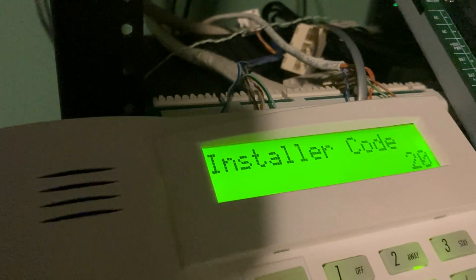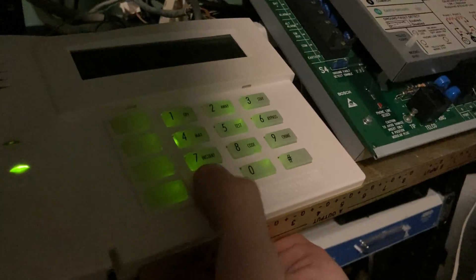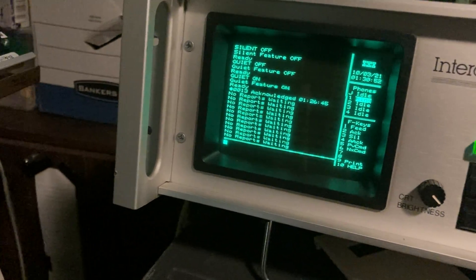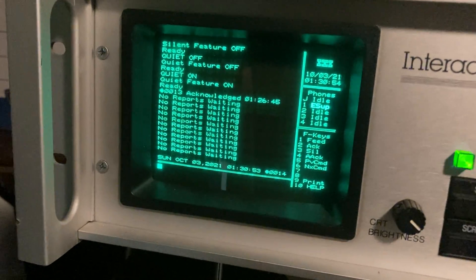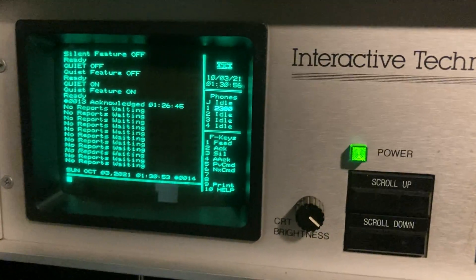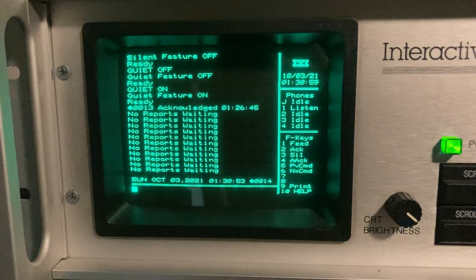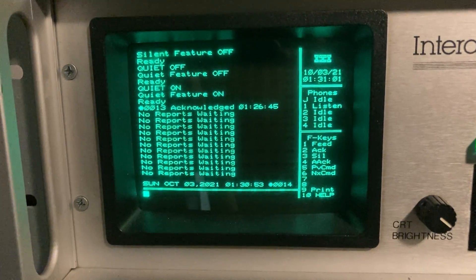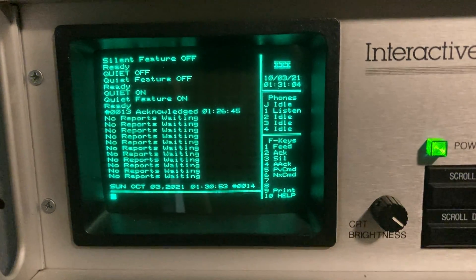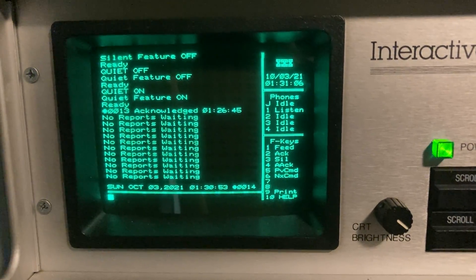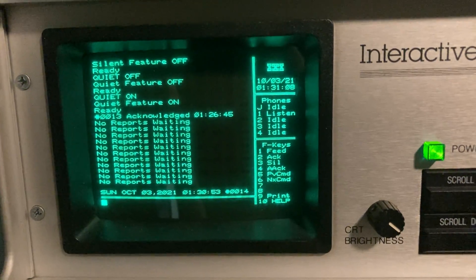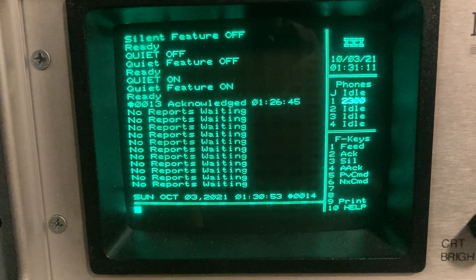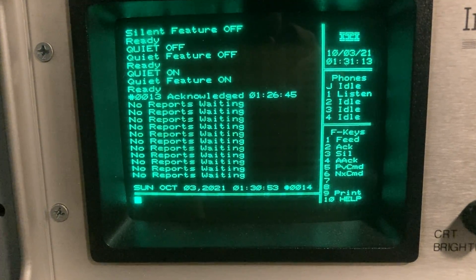And then exit programming mode. Now it's going to report a zone 2 trouble. Now 3 plus 1 format can't actually report the zone but it reports just the trouble. And I don't know if it was just not a standardized term for ITI back then or what, but troubles don't exist within this receiver, they are all called supervisory. So if you see supervisory it's probably a trouble. There we go, just acknowledge.